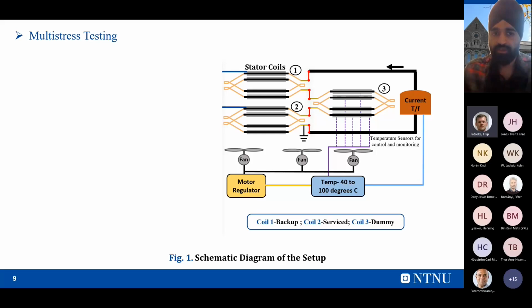So these are the coupling capacitors. And why am I using two? Because for each coil we have to measure the partial discharge separately. The purpose of using this filter is so that there is no interference in the measurement. So they have a separate measurement for the first stator coil and a separate measurement for the second stator coil, and further they have some quadrupoles and PD detectors.